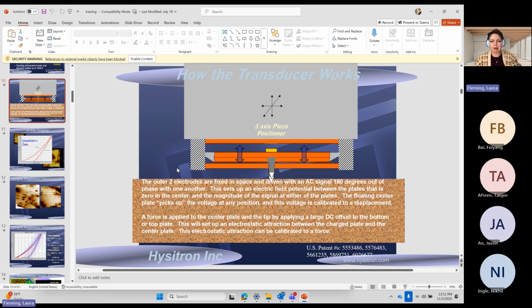The force is applied to the center plate by applying a large DC offset to the bottom plate. This is bottom or top, but it is the bottom. It sets up an electrostatic attraction, and it causes that to move down then. We then have that also calibrated to a force, which is called your load scale factor. So each transducer is unique, and that comes with a calibration sheet that will have that information on it.